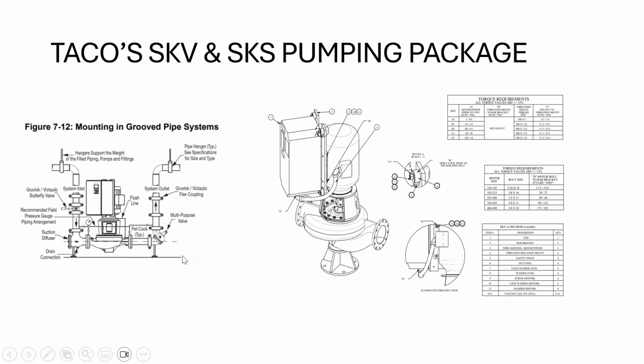Groove piping is fine. You can see we got a little stanchion in here to move it out as well. So here's some of the installation requirements that are shown here, torque requirements. I'm not going to get into that, but for the different motor sizes, the bolt sizes, we actually have some torque specifications. Don't let that out of the bag. Some of you might know. Anyways, and then the bill of material is shown here for all of that as well. So it is pretty important and critical to make sure everything's properly taken into account in that regard.